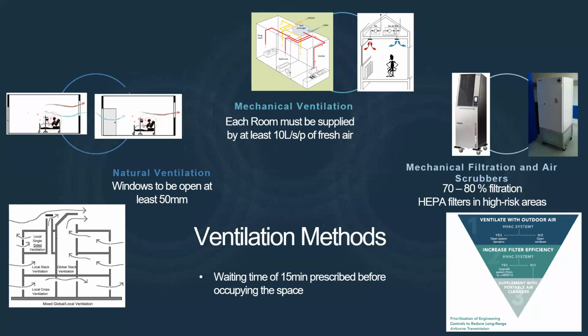Now, I've also indicated a drawing on the bottom left corner of the slide with the type of airflow measures that you could look at. And as you can see in this document, there's multiple ways in how to conduct cross ventilation or single side ventilation through either one or two openings in a specific room. So typically what a hospital in South Africa consists of is a combination of fresh air and mechanical ventilation, which we would discuss just now. And it also gives you the benefit of the better of the two situations, depending on the type of area that you would work typically in. So that's the natural ventilation section.